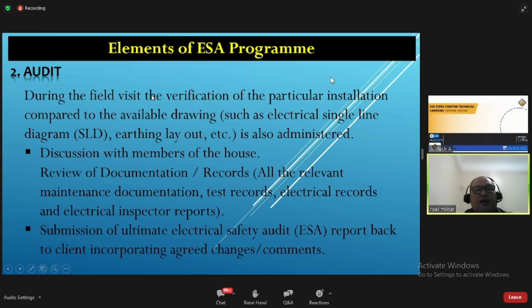In my experience conducting electrical safety audits in buildings, there were modifications in terms of the single line diagram, where the electrical plans I asked for during the audit differed from the actual situation. This might be from 5 or 10 years ago, where I would also ask for the plan of the building in order to reflect all the connected loads of the entire facility.